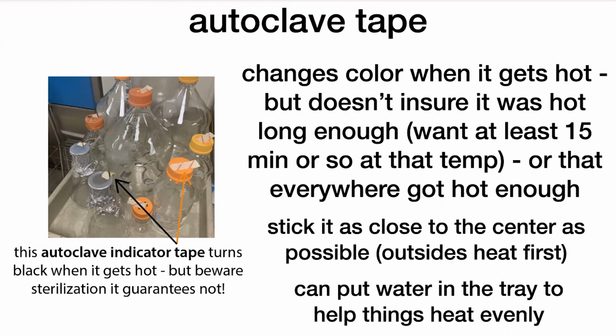But in order to actually sterilize things, you have to keep things at that hot point. Typically this is at least 15 minutes or so, and it depends on what you're trying to sterilize as well as what types of things you're trying to kill. You want to make sure that you were at that temperature long enough, which the autoclave tape can't tell you. So you kind of have to trust it, or there are different methods you can use if you really, really need to make sure that things got sterilized.